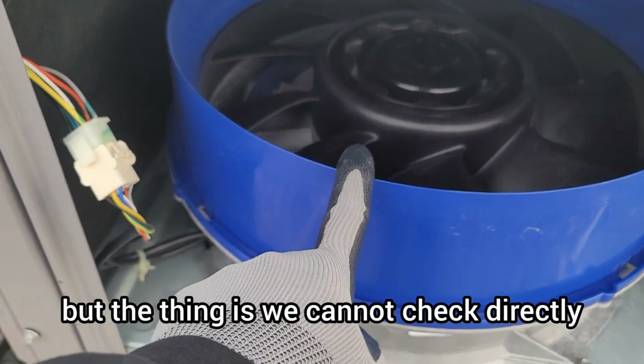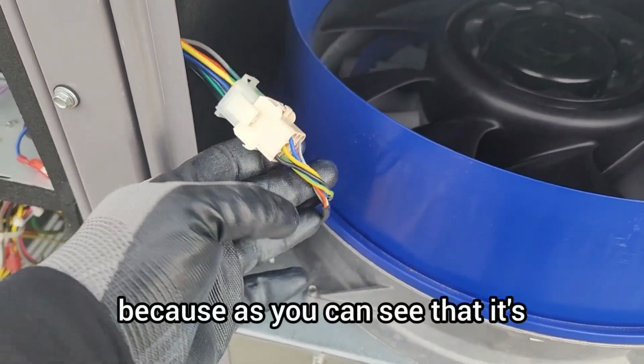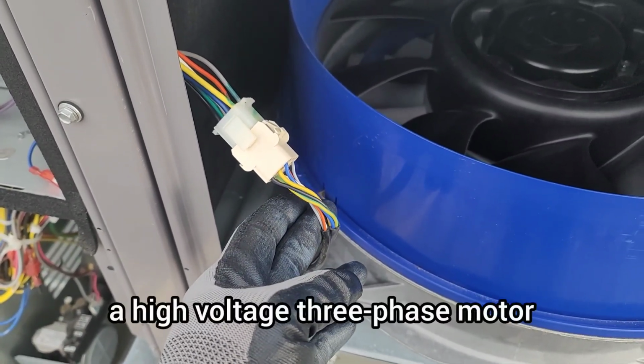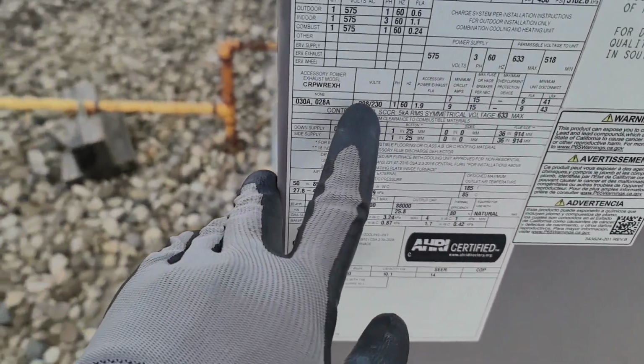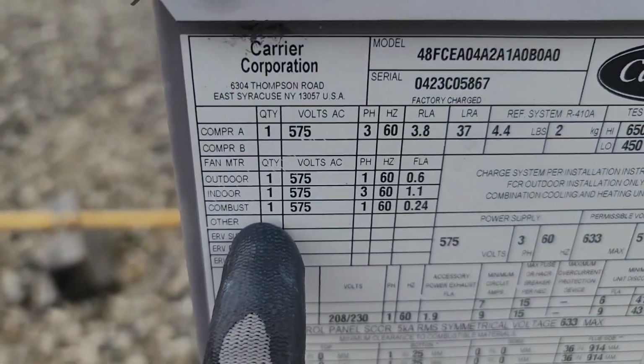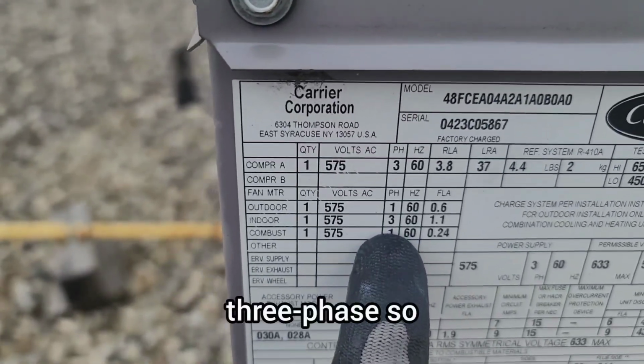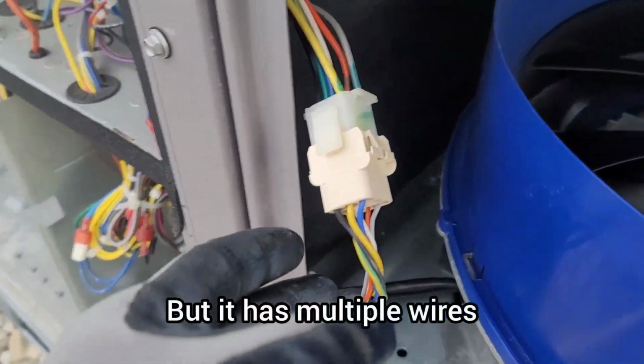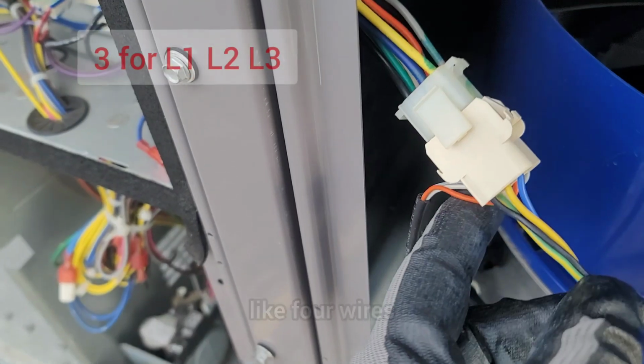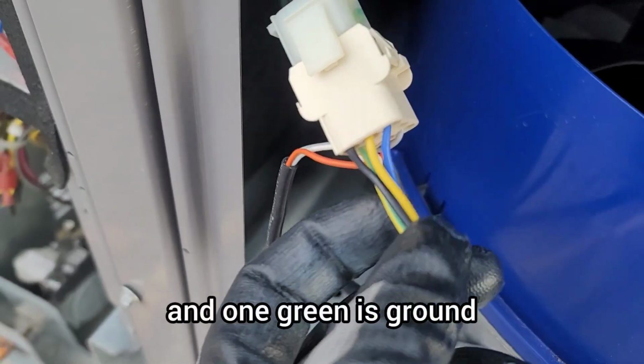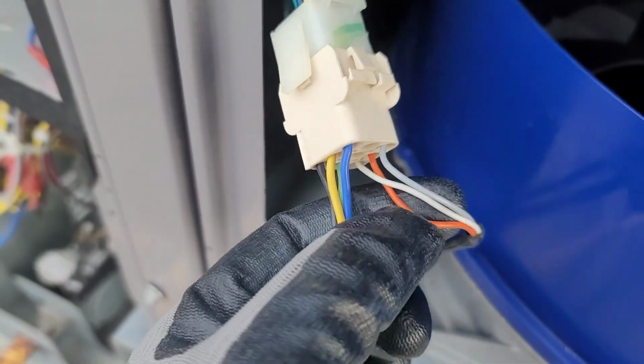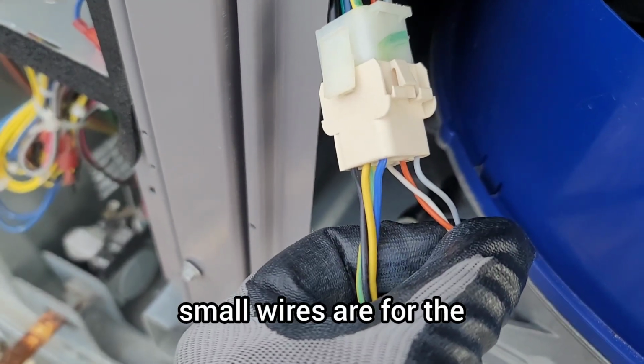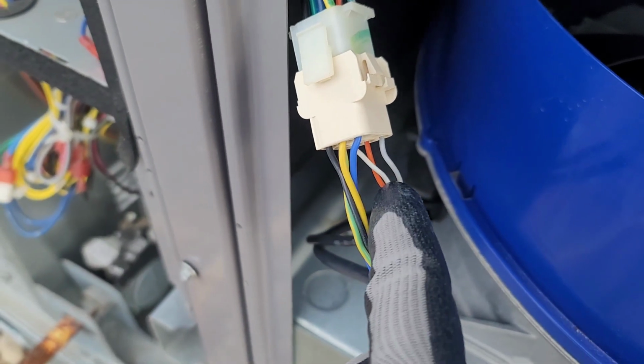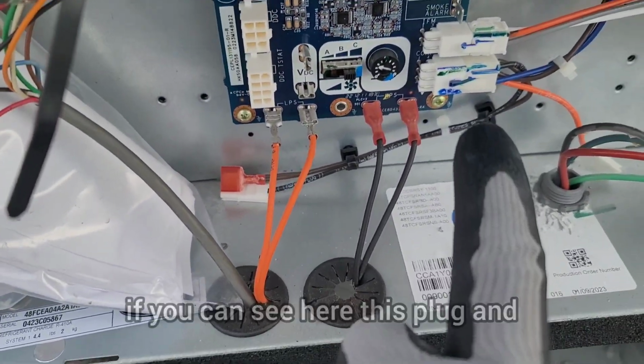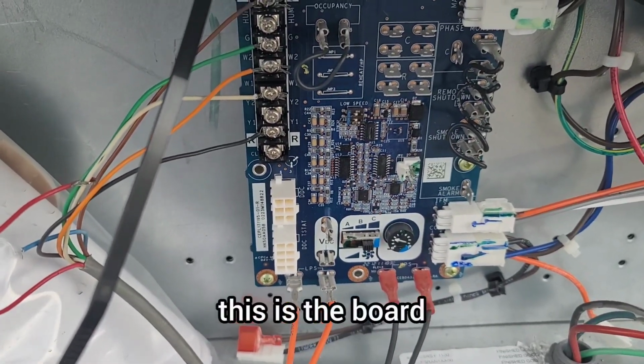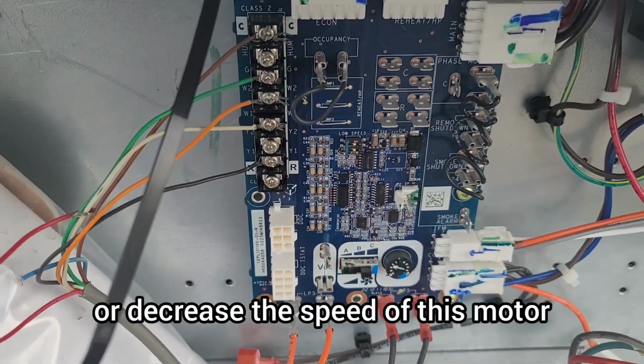But the thing is, we cannot check its winding directly through this plug, because as you can see, it's a high voltage 3-phase motor. If we check the spec label here, it says indoor motor 575 3-phase. Here it has multiple wires, like 4 wires: 3 would be the phase and 1 green is ground, and all these small wires are for the speed, which is connected here. If you can see this plug, this is the speed board where we can slightly increase or decrease the speed of this motor.